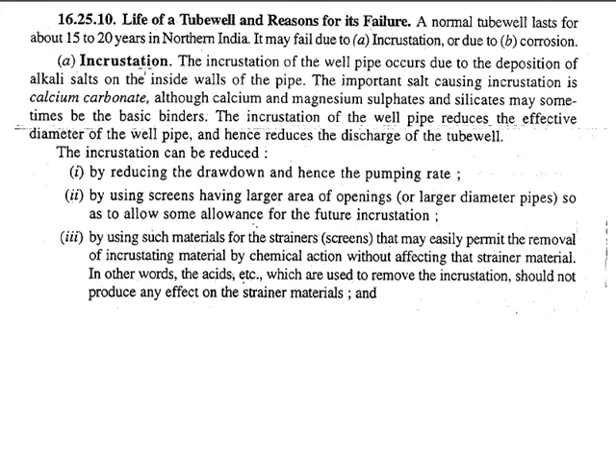In the case of incrustation, there is deposition of alkali salts on the inside wall of the pipe. One of the important salts causing incrustation is calcium carbonate, which is the main component responsible for incrustation of tubewells. When this happens, there is obviously a reduction in the discharge through these tubewells.